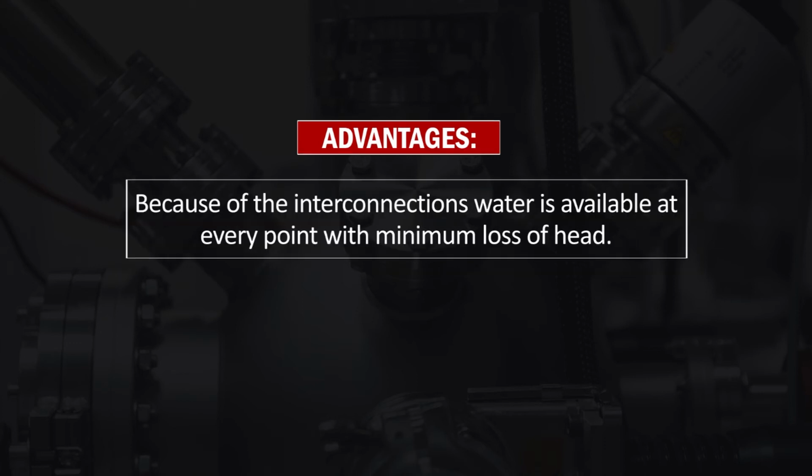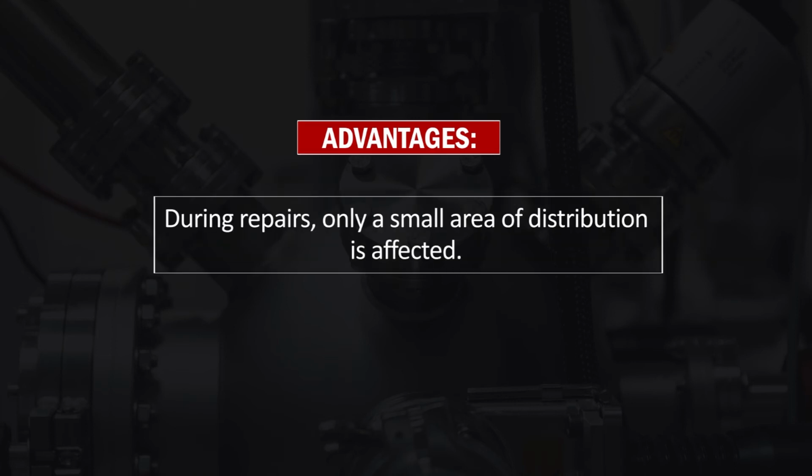Advantages: the free circulation of water without sediment deposit minimizes the chances of pollution due to stagnation. Because of the interconnection, water is available at every point with minimum loss of head. Enough water is available at street fire hydrants as the hydrants draw water from the various branch lines. During repairs, only a small area of distribution is affected.